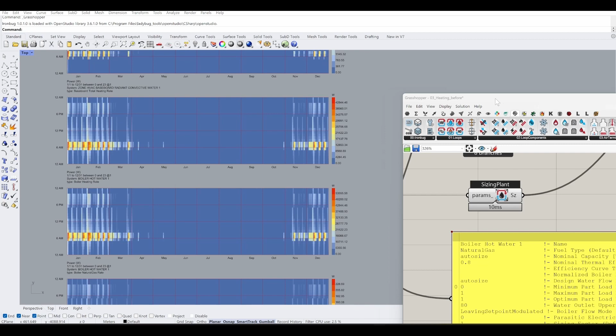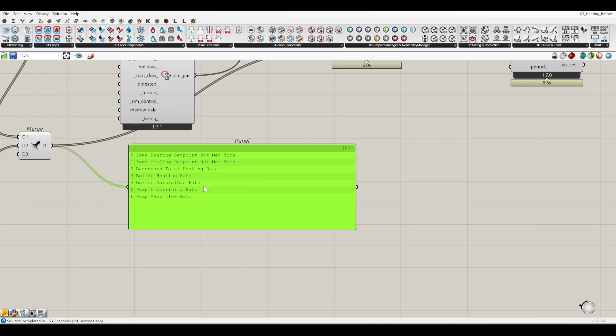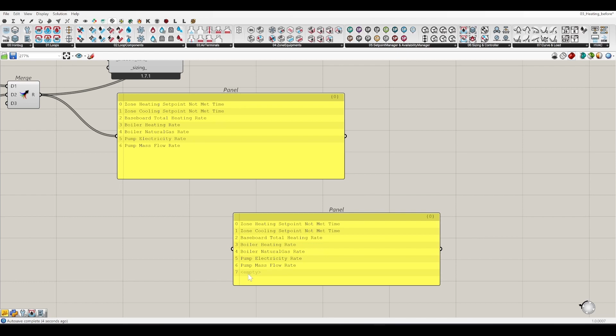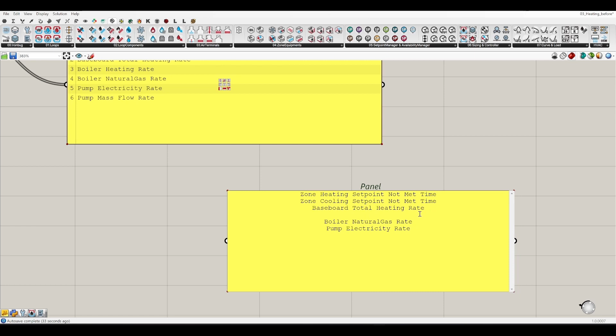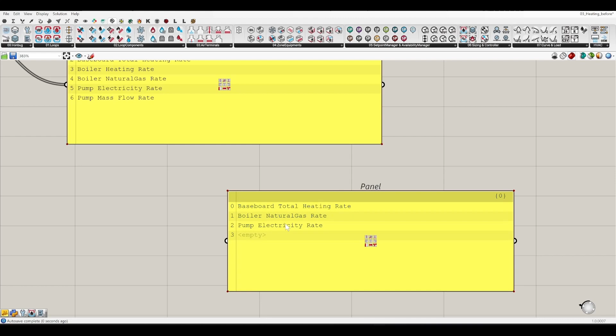Okay, now let's look at the hourly data. What we need is the initial natural gas rate. So let me copy, going to multiple lines. We already checked the efficiency of the boiler is 80% from the heating rate and the natural gas rate, so we don't need the heating rate anymore. We don't need the electricity or mass flow rate. Baseboard, okay. All we need is 3 values.